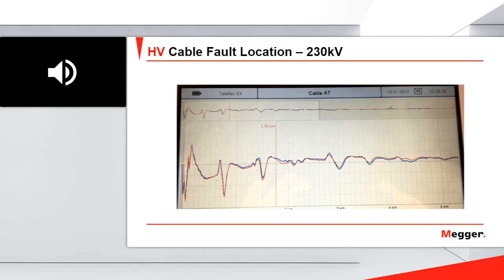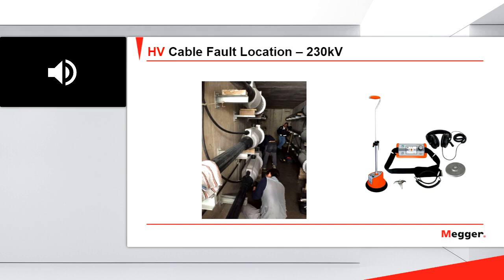Indeed, in this case it is something that the crew asked for: please pinpoint the fault because we need to break up the highway. So I did the pinpointing with the Digiphone, and the Digiphone showed me clearly that the fault was in the second splice. Here you can see the technicians of the splice factory pointing at the faulty splice. Okay, so this is a nice example of how to use the current reflection method in transmission cables.